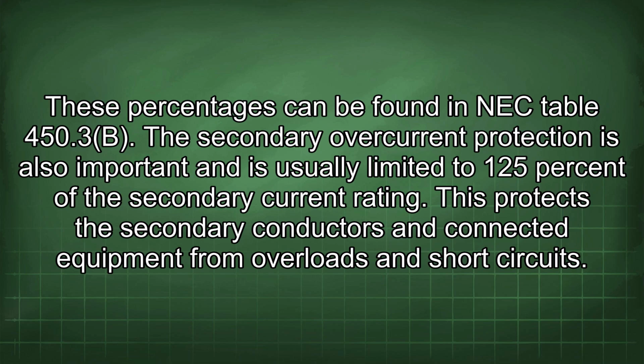The secondary overcurrent protection is also important and is usually limited to 125% of the secondary current rating. This protects the secondary conductors and connected equipment from overloads and short circuits.